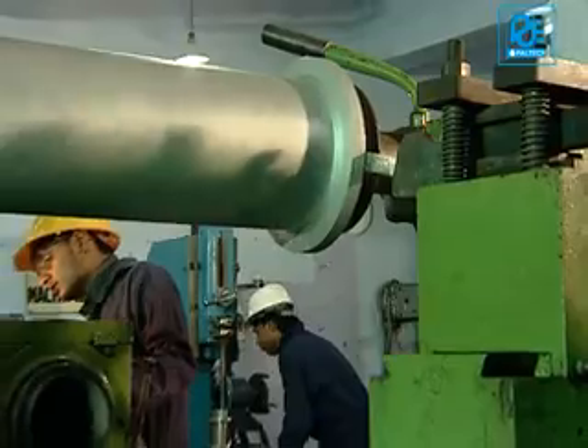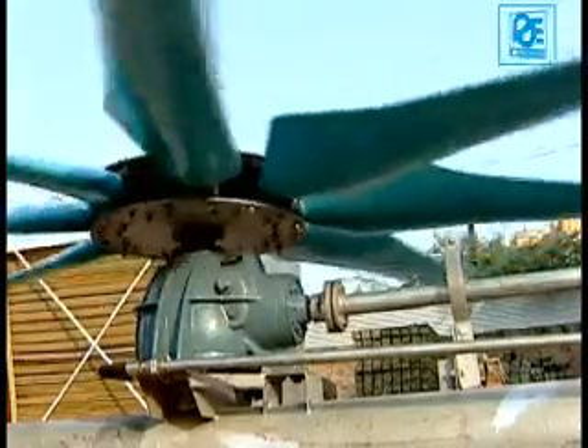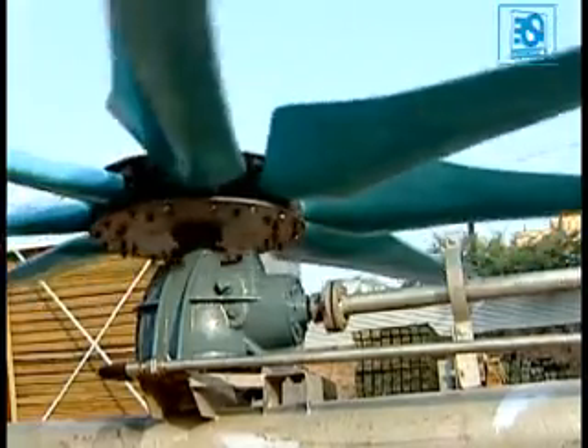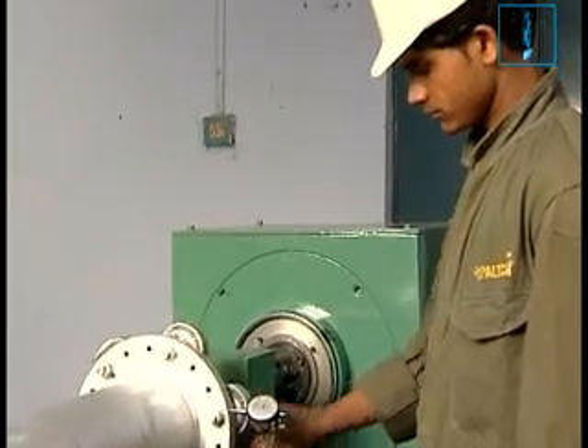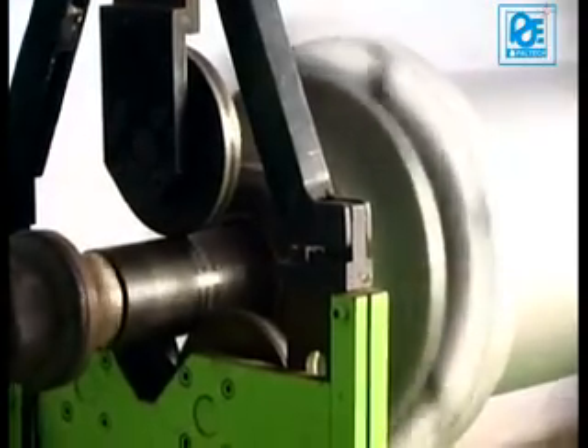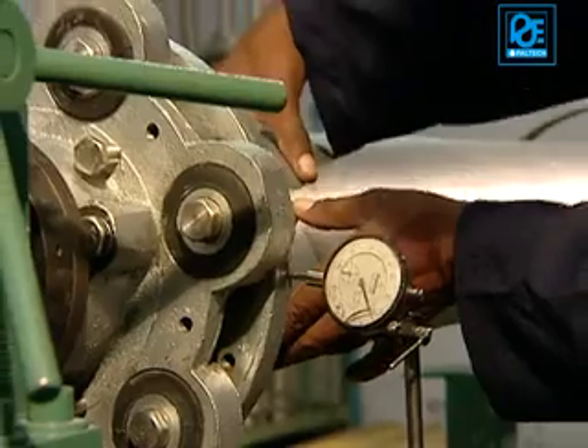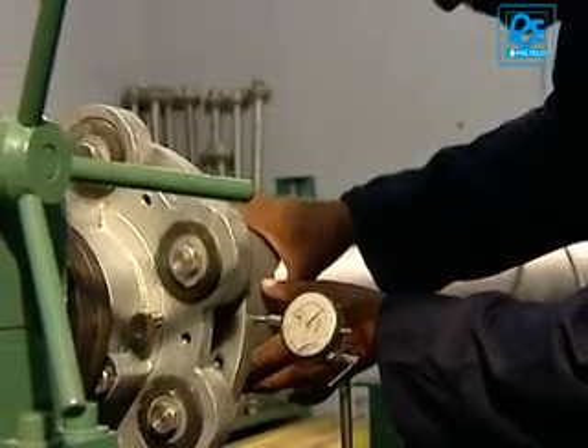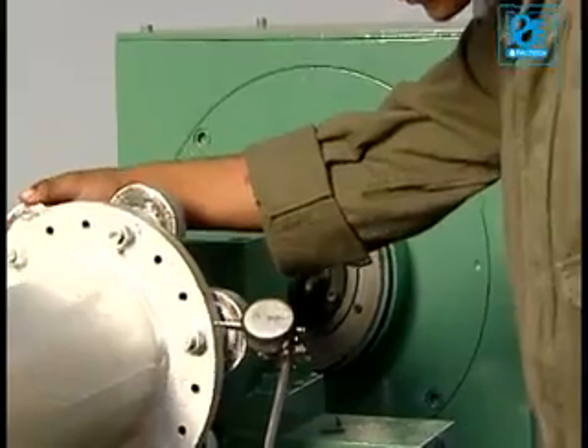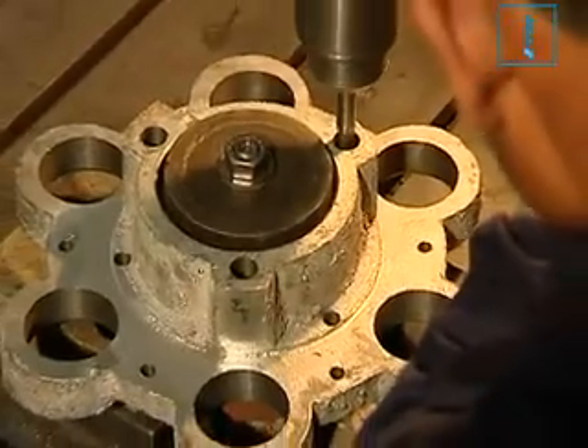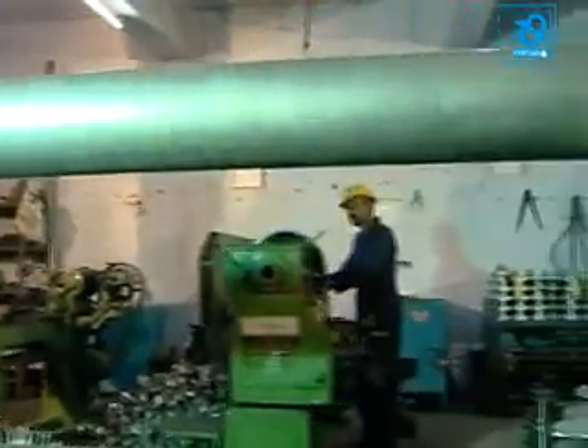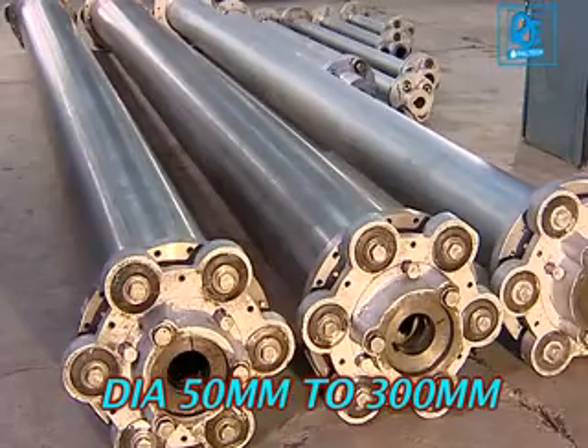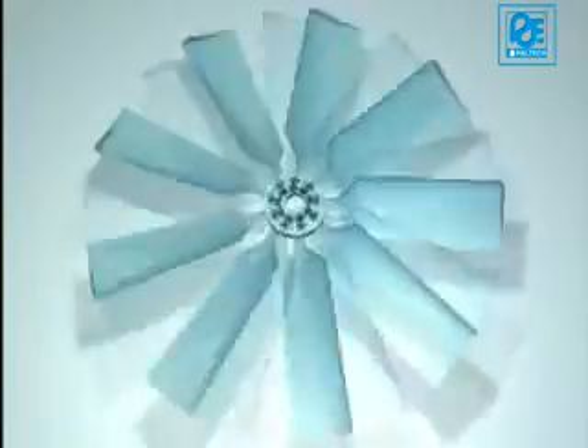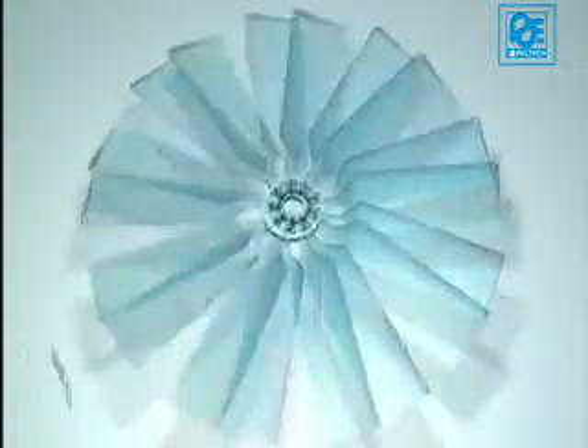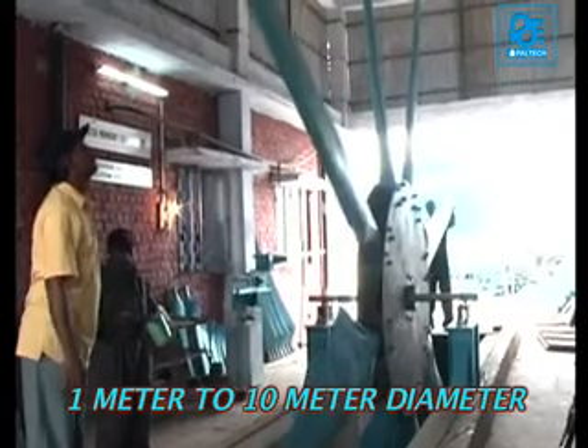The drive shaft is the crucial component of the cooling tower. It is used for power transmission for gear units. Paltech also checks run out of the tube with the help of magnetic dial indicator. After assembly, each drive is dynamically balanced on computerized dynamic balancing machine. Paltech manufactures 50 mm to 300 mm diameter drive shafts. Paltech manufactures FRP fan assemblies ranging from 1 meter to 10 meter.